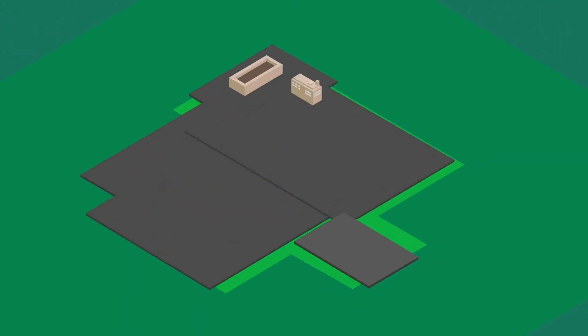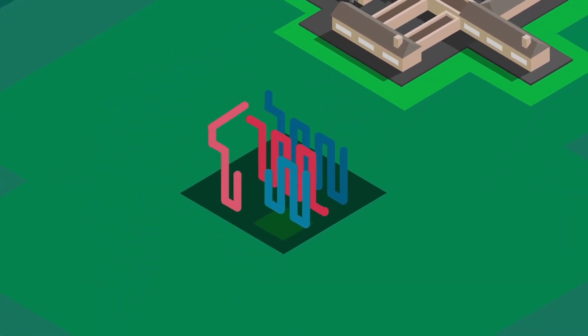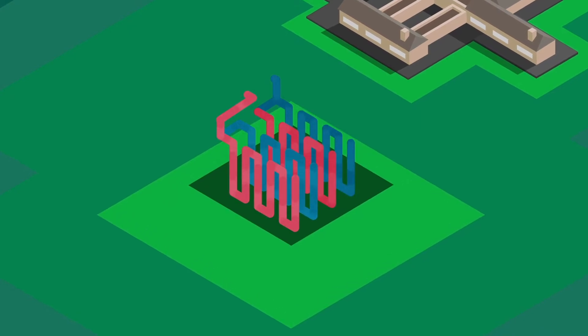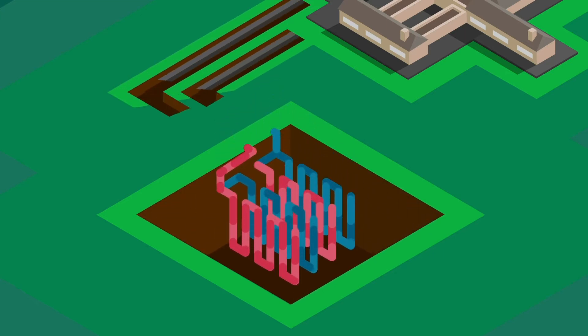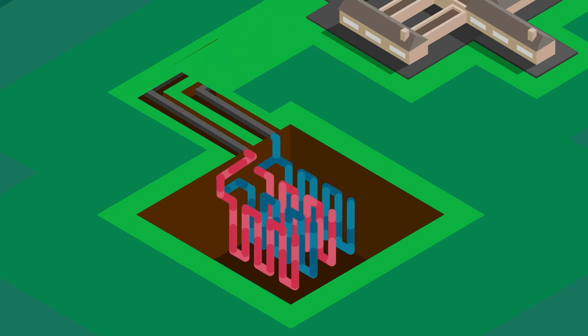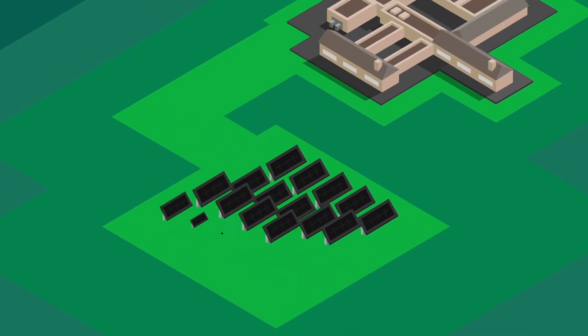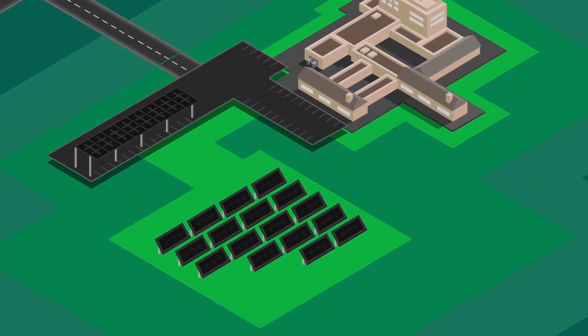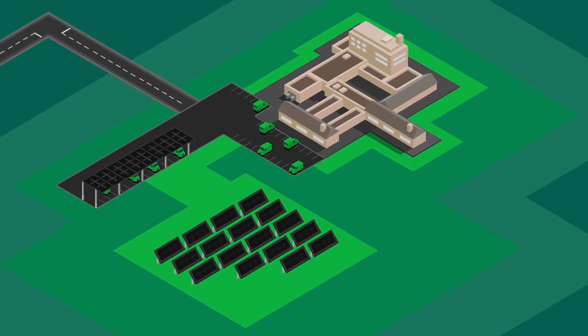So how does it all work? First, to heat or cool the Oxford Vista campus, the underground geothermal heat exchanger system will use water that circulates through the ground back to the mechanical room into a refrigerant, which is then condensed and distributed throughout the building to be used as on-demand heating and cooling. This is done through a variable refrigerant volume, or VRV, system. The system offers the ultimate in zoning control and provides energy recovery between temperature differentials throughout the building. Above the underground geothermal loop, a 434kW ground-mount solar array and solar carport combo are passively collecting energy from the sun to generate clean, renewable, on-site power.